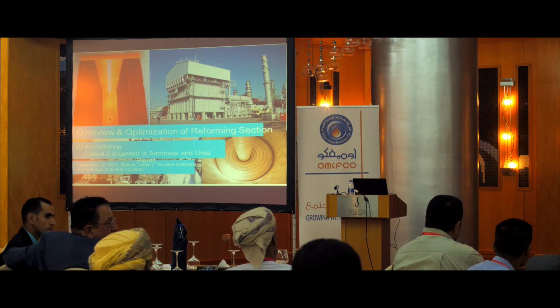What happens if you have a leakage in the ammonia source? In the pipe itself? In the pipe itself. Ammonia will disperse in the system, and you will find yourself facing ammonia leakage all the way. If the leakage is within the convection bank, it's not a big problem, because first of all the amount of ammonia you inject is very small. For these kinds of systems, we have maybe 20 kilograms per hour of concentrated ammonia. With only 20% in the solution, it's maybe 100 kilograms. So if the leakage is within the convection bank, it will go out to the stack.